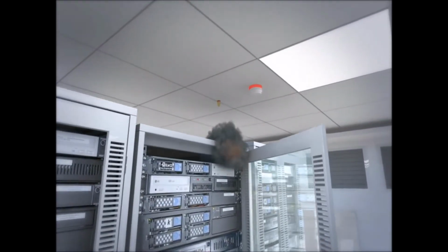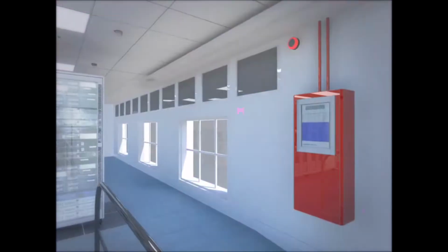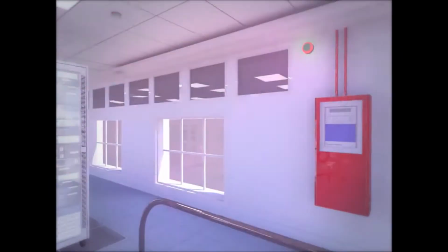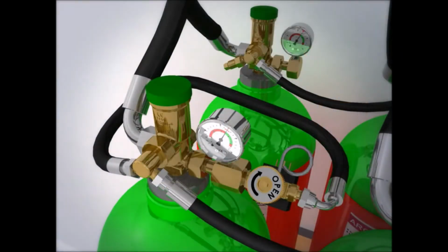The system will be configured to deliver an accurate and timely indication of a fire condition. Following the initial alarm and a preset delay, a final alarm is given and the control panel energizes the solenoid on the Argonite C60 release unit. Cylinder pressure is then directed along the actuation lines connected to the C60 cylinder valves.